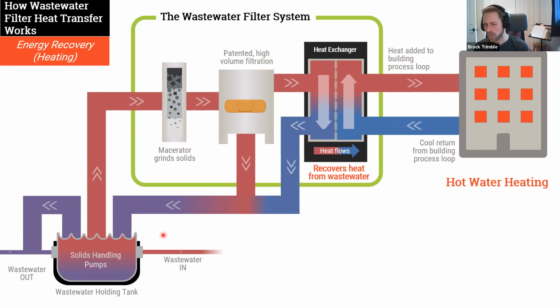If we see a typical entering temperature of around 70 degrees, we can take it down to, typically, as low as about 41 degrees Fahrenheit. It may depend on what your field design looks like and if there are any limitations that you want to see, as well as on the high end. We've seen energy rejection as high as about 90 to 95 degrees Fahrenheit using about a 70 degree entering source. So there is some variability that can be designed in for your type of project. Okay, very good.